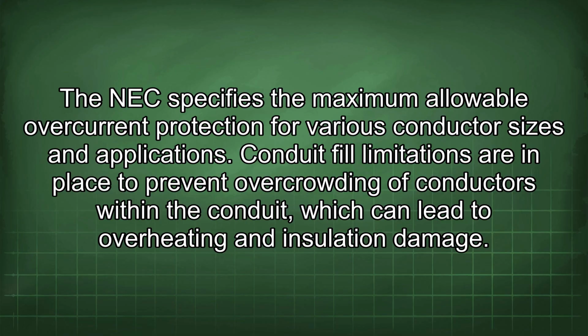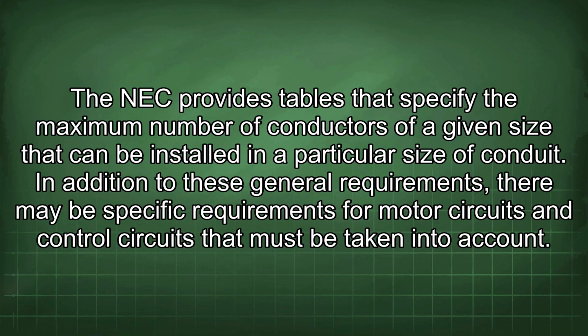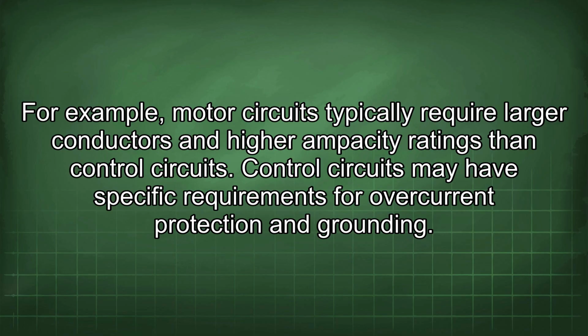Conduit fill limitations are in place to prevent overcrowding of conductors within the conduit, which can lead to overheating and insulation damage. The NEC provides tables that specify the maximum number of conductors of a given size that can be installed in a particular size of conduit. In addition to these general requirements, there may be specific requirements for motor circuits and control circuits that must be taken into account. For example, motor circuits typically require larger conductors and higher ampacity ratings than control circuits. Control circuits may have specific requirements for overcurrent protection and grounding.